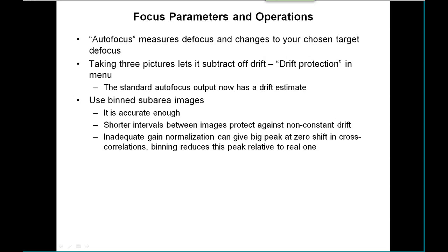The amount of shift tells us how far away the specimen is from the focal point. The auto-focus button or the option in the Focus menu measures the defocus with this method and then changes to the target defocus — the number you've chosen. You'll see it take three pictures unless you've turned off the drift protection option, because it protects against drift by measuring the drift from the shift between each pair of pictures and subtracting that off. There's also a nice estimate of the drift in nanometers per second any time you auto-focus.